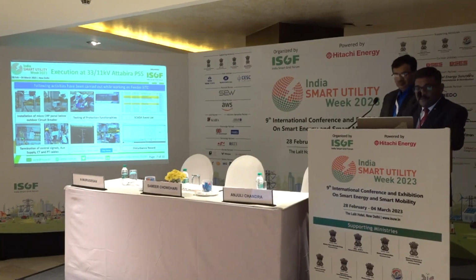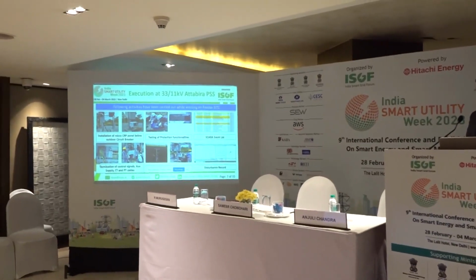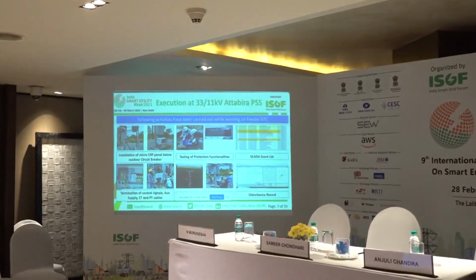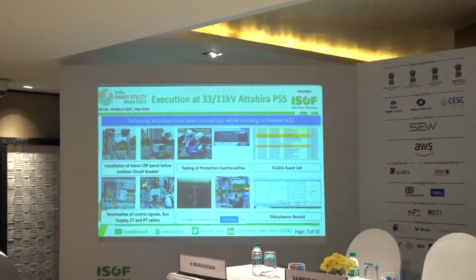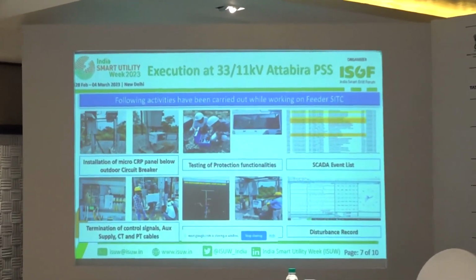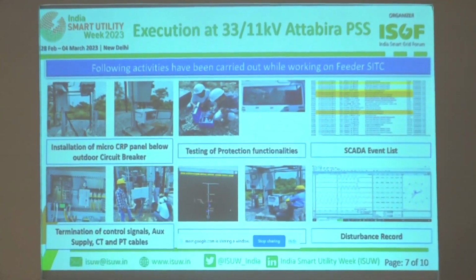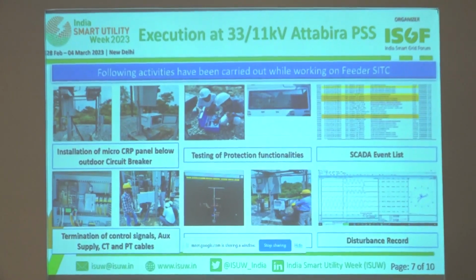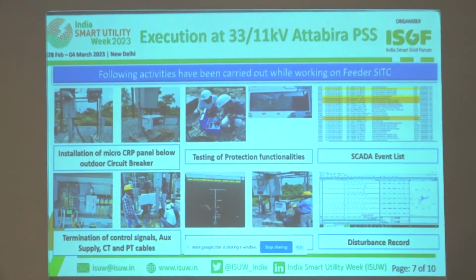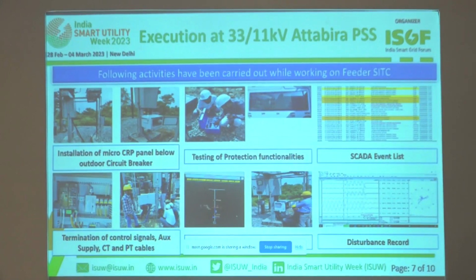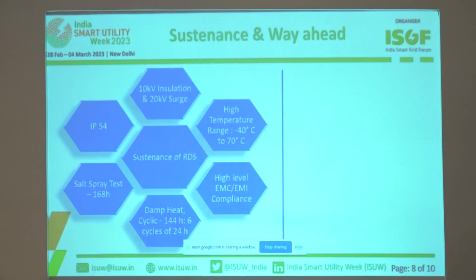This is the execution where we implemented the RDS project. Earlier there was no CRP panel below the transformer and circuit breaker. So we installed this micro CRP there, and it communicates with SCADA, and the units we installed are able to give disturbance records also at one central location. We have implemented this successfully at our substation, and we have taken care of the sustenance part also.